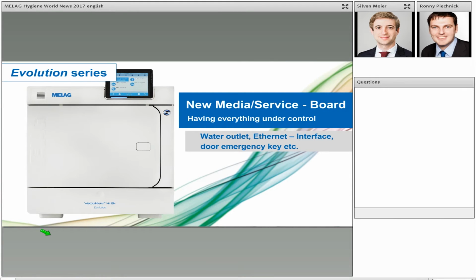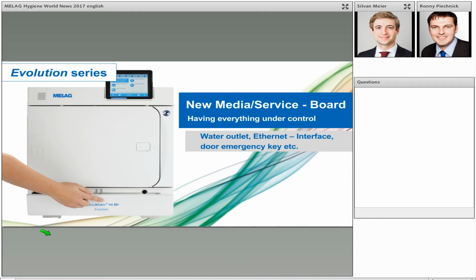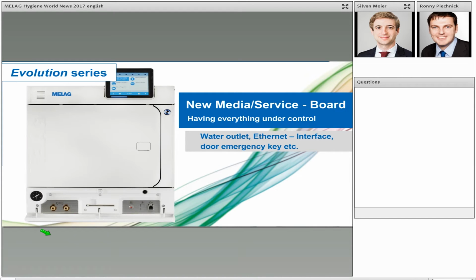And a second new feature that we are proud to announce is our new media board. In the past, it has been a little bit complicated for you when opening our front panel. But now, by simply clicking on the front of the autoclave, you can open the new media board, and you have everything in one place quite neatly. You have a manometer that displays the pressure of the double-jacket steam generator. You have quick fitting connections for refilling and draining the storage tank. You have a reset button for overheating protection, and you also have an Ethernet data connection. So everything in place quite neatly that allows you to access everything you need quite conveniently.